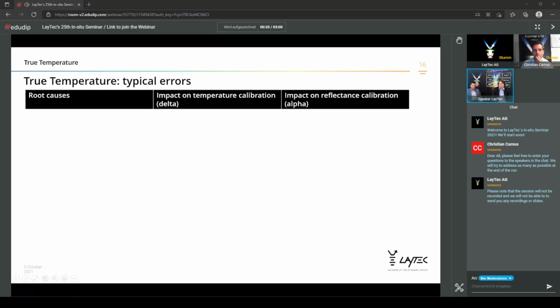Yes. So, as Oliver explained, there's a high importance that the boundary conditions are maintained and all fulfilled in order to achieve a consistent, correct, true temperature. Now, this is going to list some typical root causes or errors we see, and have seen over our time of field service support and direct customer or user support, and which we are typically still seeing today. So it doesn't mean that the entire environment is causing many errors, but it's mainly the errors caused by wrong operation or wrong handling.